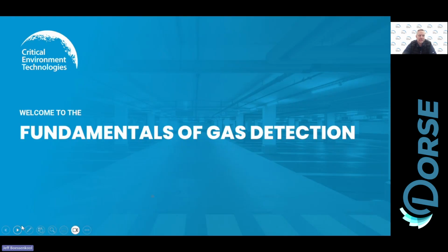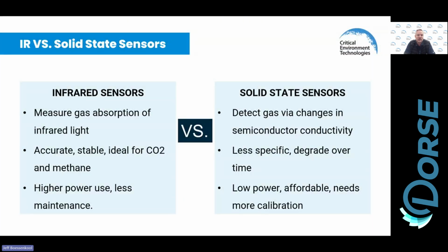Okay, and I'm going to talk a little bit about that because within the industry, what we've seen over the last few years is that when it comes to monitoring of refrigerants, if you think about a typical chiller room where you've got a couple of chillers in there, there can be other off gases or other gases that are present in that room. If you think about maybe paints or solvents that are inside of that room, maybe some cleaning products, they can in fact cross-contaminate or poison a solid-state sensor. And we have seen a number of instances of that, and not just our company, within the gas detection industry.